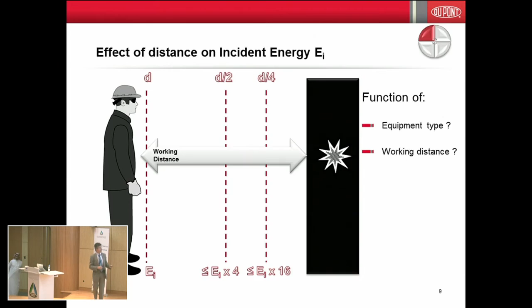To simplify, if you divide the distance by 2, the incident energy will generally be multiplied by 4 - it's a relation to the square. If you divide by 4, you multiply by 16. The closer you get, the more your body represents a bigger surface and will receive more energy. But that's critical, because maintenance isn't done meters away - workers have to get closer to the equipment, exposing their bodies to more energy.